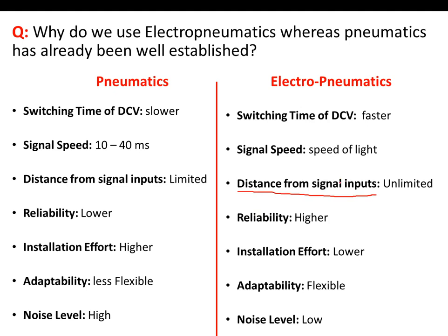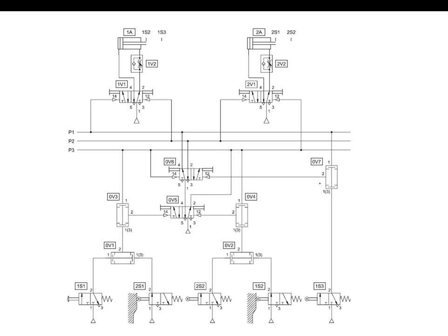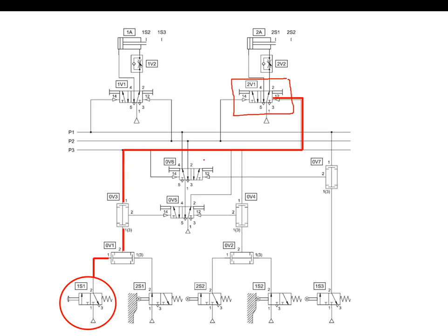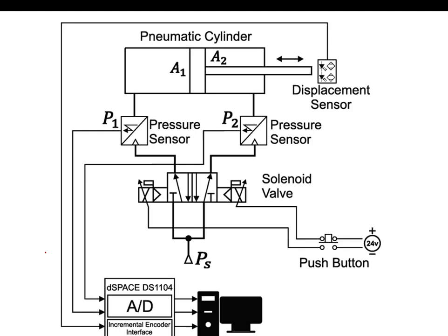Thirdly, and this one is going to be highlighted more specifically, the distance from the signal input. In a pneumatic circuit, the signal has to travel all the way from the signal input through the pipes and tubes to our final control element. As the input button gets farther, the distance becomes longer and longer, incurring losses in terms of pressure drop. Whereas in an electro-pneumatic system, we only have electric current flowing through wires, so we overcome this shortcoming.